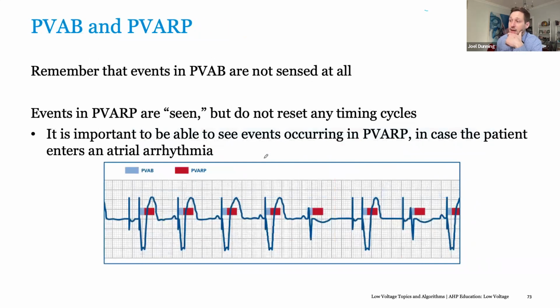Things to keep in mind. Now, you don't want to just bump out your PVARP and your PVAB. That can actually go too far, because that can affect a number of things like your 2-to-1 block rate or your device's ability to track high rates. With ICDs, it can affect your ability to discriminate atrial versus ventricular driven events because you may be undersensing atrial events. So PVARP, PVAB, all these timing cycle programmings really come down to the specific patient, right?